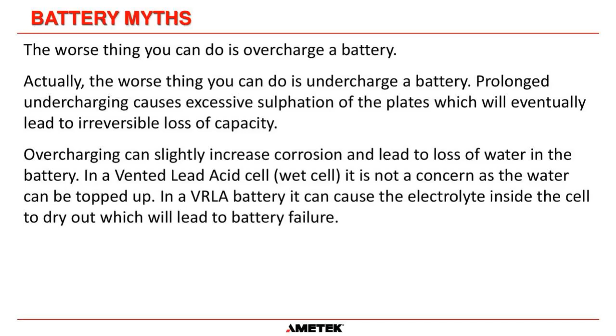Overcharging can slightly increase corrosion and lead to loss of water in the battery, but in a vented lead acid cell, that's not a concern because we can just top it up with water. In a valve regulated battery, it can cause the electrolyte inside the cell to dry out, which will eventually lead to battery failure, and it could cause the battery to go into thermal runaway. But I would say the worst thing you can do is undercharge a battery, because if you do it for a prolonged amount of time, the battery is useless.